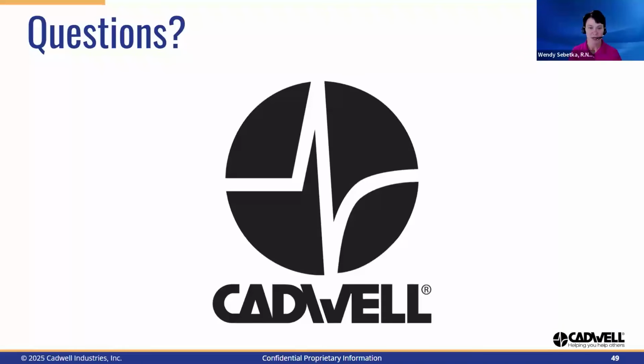Next question is, assuming the machines are using the same electrical source with ground and only one machine is working normally without noise, are the other two machines' problems hardware or grounding issues? The place where I would start with that is grounding. If the other machine is working as expected, there's something going on with those other two machines. It could still be an environmental factor based on where those other two machines are located, but I would definitely start with reviewing the grounding of those devices.